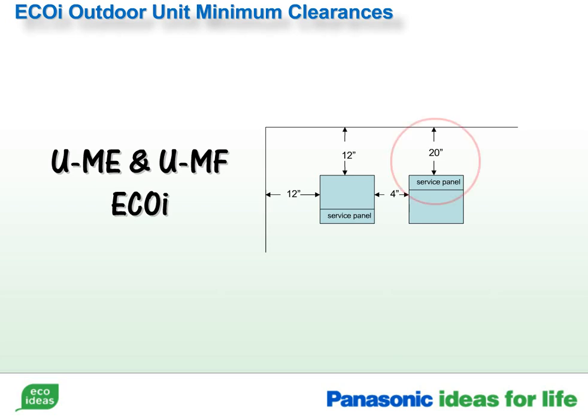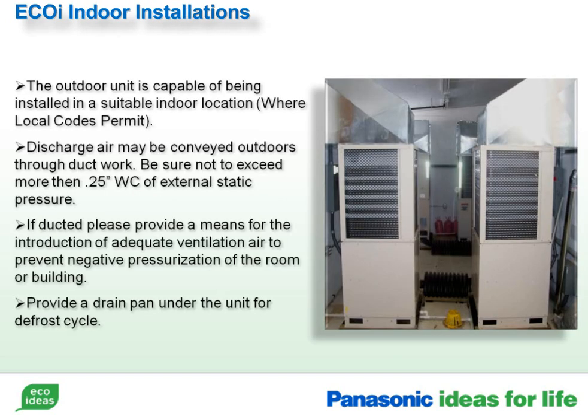As a guideline, the service panel must have at least 20 inches of clearance for future maintenance and repairs. For proper airflow around the condenser, you should maintain at least 12 inches. When combining condensers, in some situations you may place the condensers as close as 4 inches apart. The outdoor unit is capable of being installed in a suitable indoor location if your local codes permit.